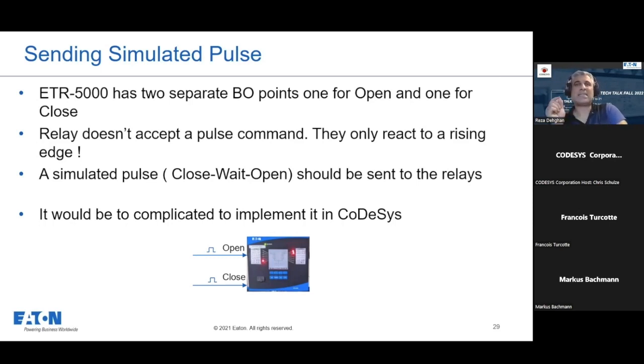So basically they couldn't receive a pulse. They could only see a switch on that point, on that line, to be close and then open, and it would consider that as a pulse. So we had to simulate this pulse with close, wait, and open. That was the way we were sending open close to the relay. So still two separate points, but on each of them we needed to simulate a pulse using close, wait, open. It's not impossible to do this in CODESYS, but we had a more straightforward option using our automation function in SMP Gateway. Because in automation function, we already support a function which is called the command conversion or control conversion.